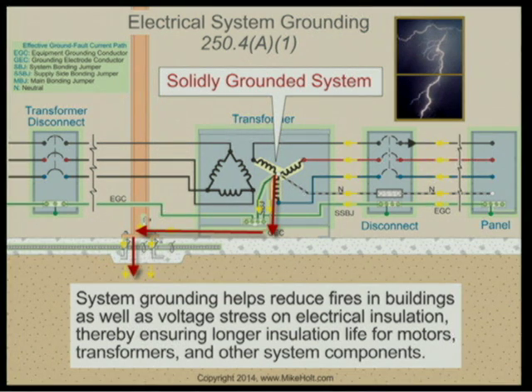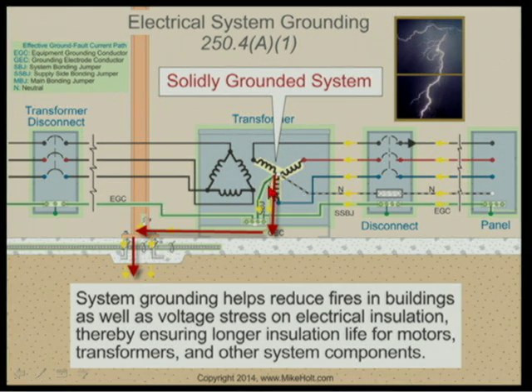Let's talk about a grounded system. A grounded system — take a look at this winding. Here's a Y secondary. It's insulated conductors, and all the conductors leaving the windings are all insulated. Except look right here: we take the actual winding itself, we run a wire down the grounding electrode conductor over to structural steel, which is ultimately connected to the earth. So now we've taken this system and we grounded it. Why do you ground a system? You ground a system because of those eight conditions Beeman explained — including lightning and all these different things. You can have an overvoltage on the ungrounded system, and this capacitive charge, the induced energy on those conductors, could cause equipment failure. So you ground a system.